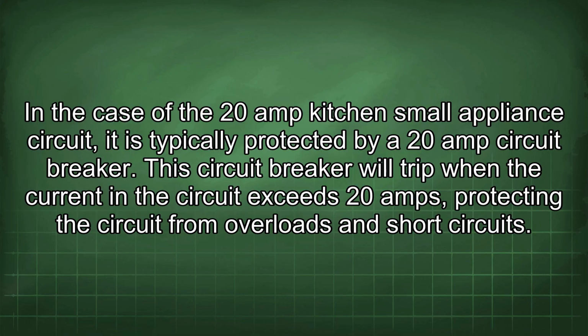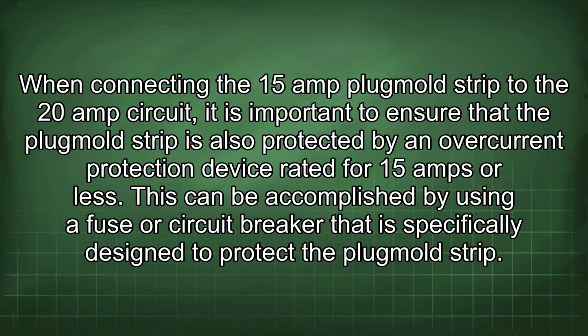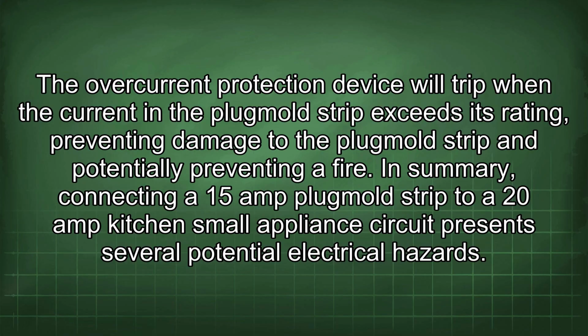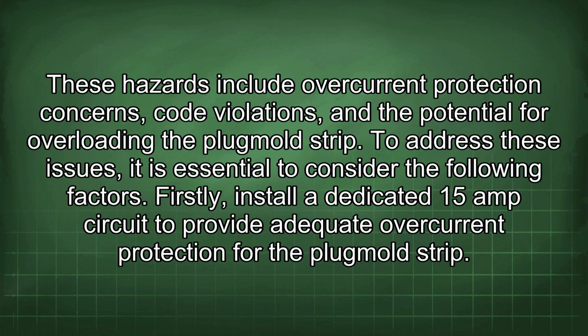This circuit breaker will trip when the current in the circuit exceeds 20 amps, protecting the circuit from overloads and short circuits. When connecting the 15 amp Plugmold strip to the 20 amp circuit, it is important to ensure that the Plugmold strip is also protected by an overcurrent protection device rated for 15 amps or less. This can be accomplished by using a fuse or circuit breaker that is specifically designed to protect the Plugmold strip. The overcurrent protection device will trip when the current in the Plugmold strip exceeds its rating, preventing damage to the Plugmold strip and potentially preventing a fire. In summary, connecting a 15 amp Plugmold strip to a 20 amp kitchen small appliance circuit presents several potential electrical hazards. These hazards include overcurrent protection concerns, code violations, and the potential for overloading the Plugmold strip.